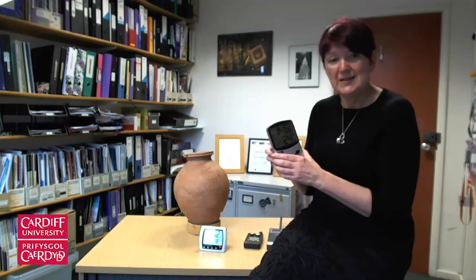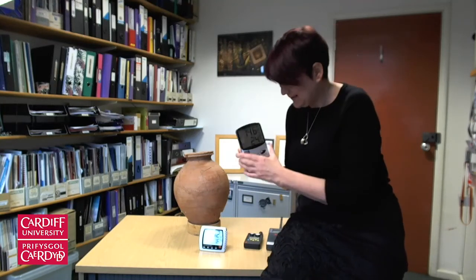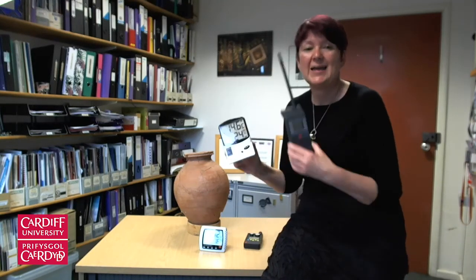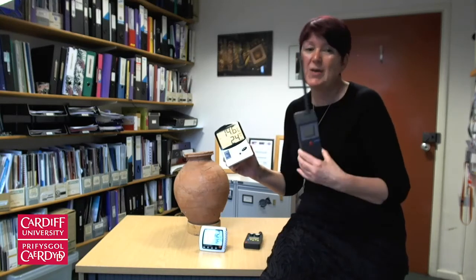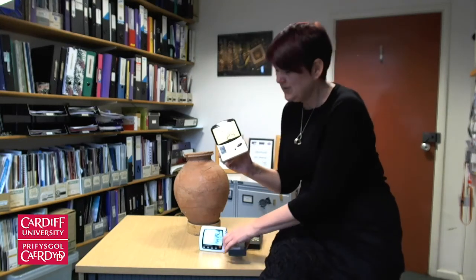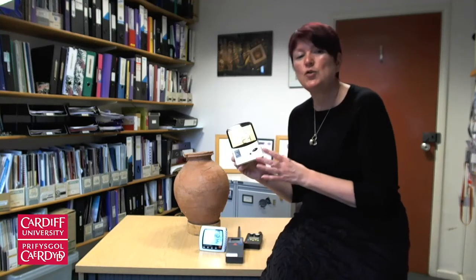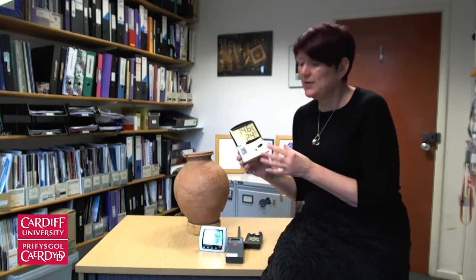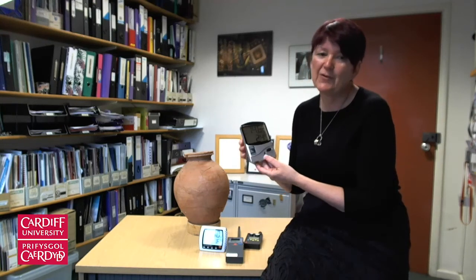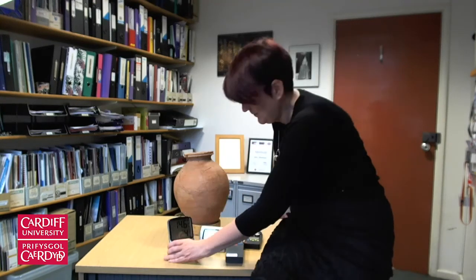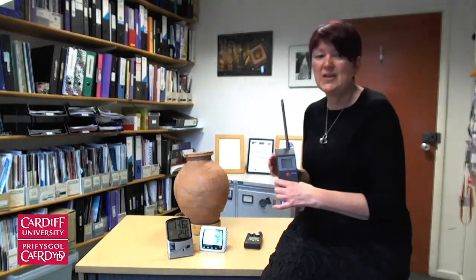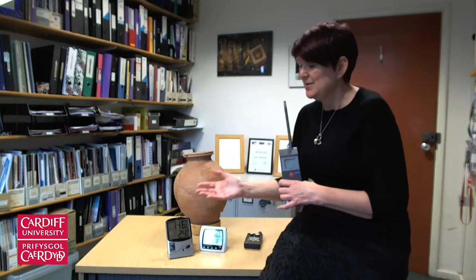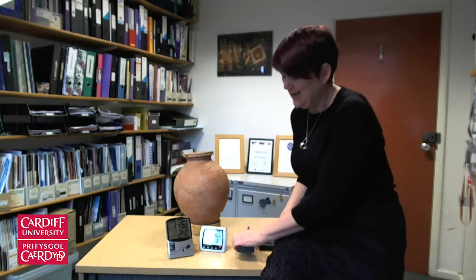These are quite simple and relatively cheap, but normally can't be calibrated. So you do need to perhaps at least cross-check them against a calibratable meter, against one that you can properly check, just to check that they're in the same zone. Don't get too worried about 1 or 2% difference, because something like this will probably have an accuracy of plus or minus 3 or plus or minus 5. And something like this will have an accuracy of plus or minus 2. So if you add those two accuracies together, if they're within 5% relative humidity of each other, then that's going to be as accurate as you can expect.